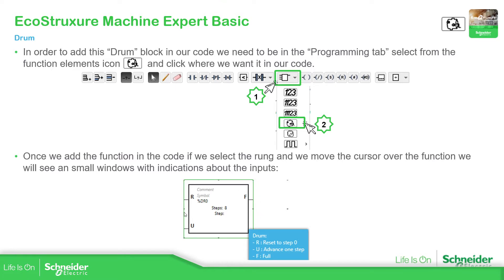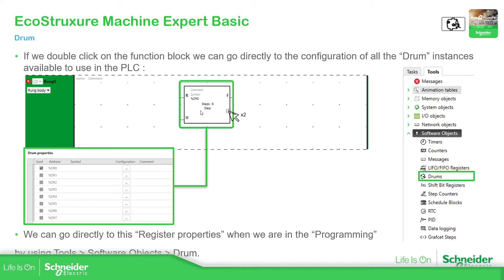You can see there are only two inputs and one output. The input R is for reset, U is for advancing one step — just like an increment — and F is to indicate that all steps have completed. To access the full configuration, double-click to open the drum properties, where you can see all drums available. Another way is via Programming Tools > Software Objects > Drums.